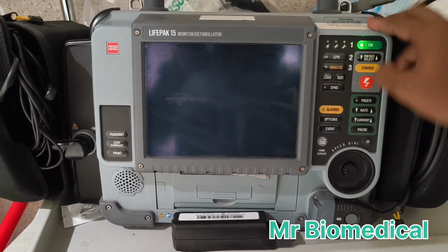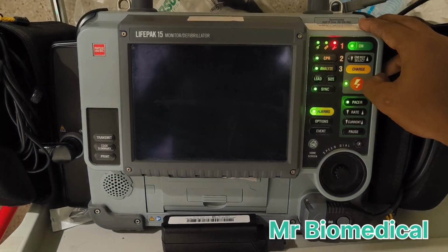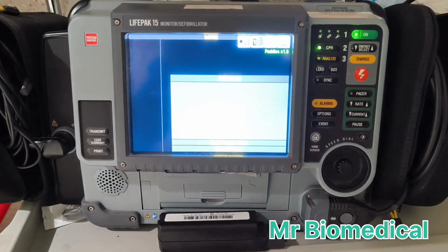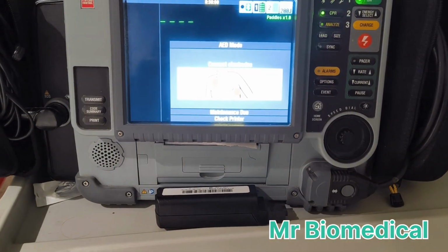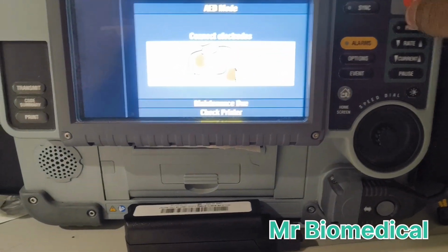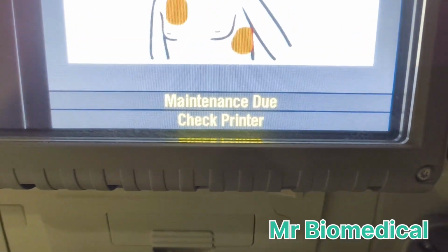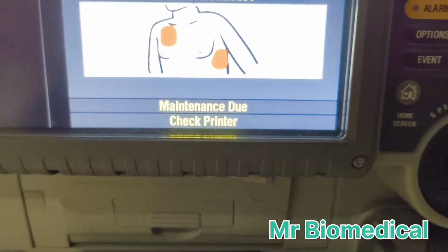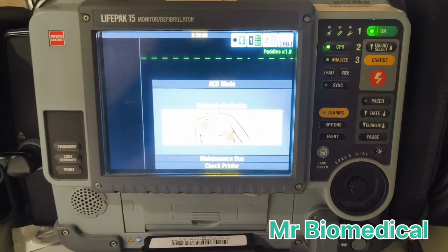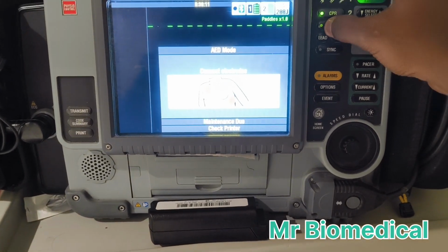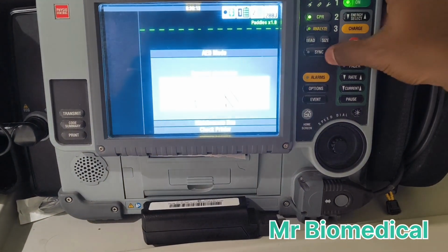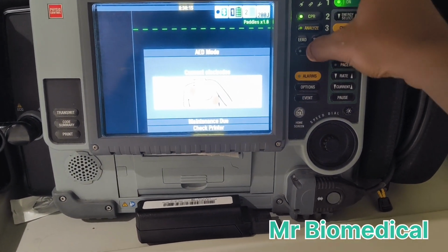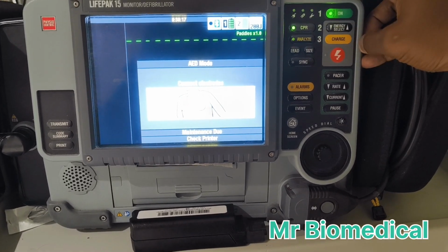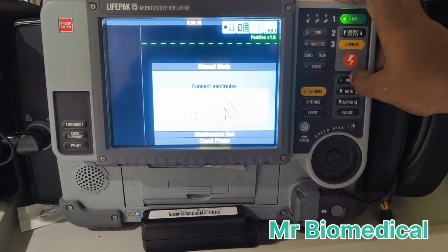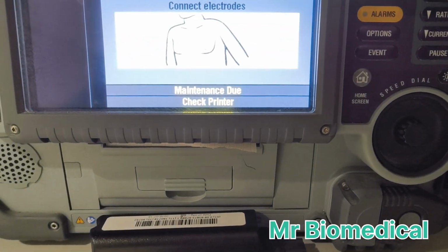So hi guys, in this video we are going to see the calibration of the Lifepak 15 defibrillator, and as you can see there's a message about maintenance due and the printer. So this is in AED mode, and it says connect electrodes.